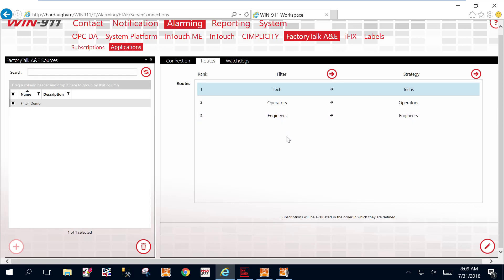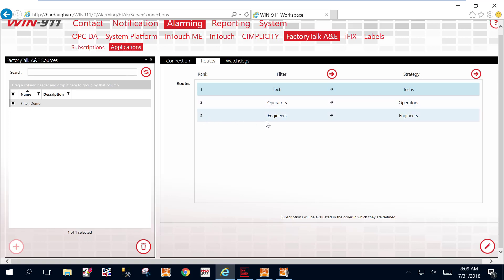And then we have all of our filters made. So what's going to happen down the list is alarm comes in. It's going to be checking this filter. Does the alarm have this criteria, which would be does it have the word drive in it? No. Does it have this one? No. Does it have this severity? Yes, it has a severity. So it's going to start to do this call out to the engineers. So you're allowed to push these up and filter however you want. But they do go down sequentially down the list until you catch something.